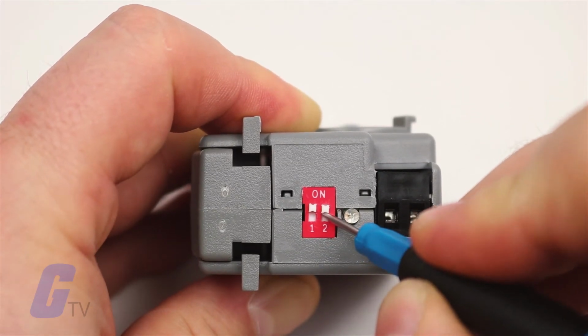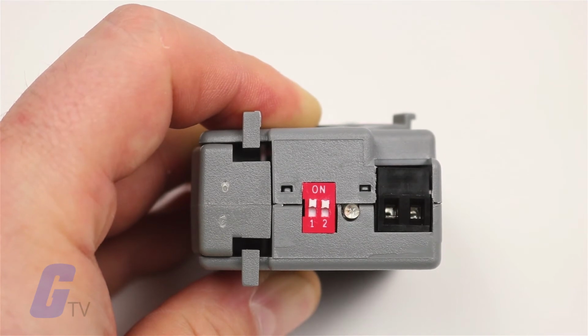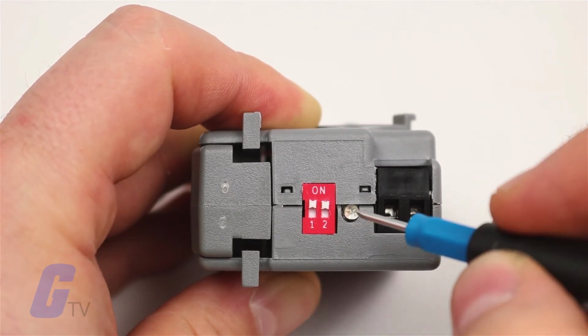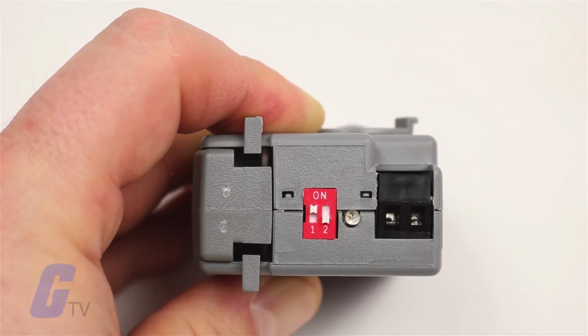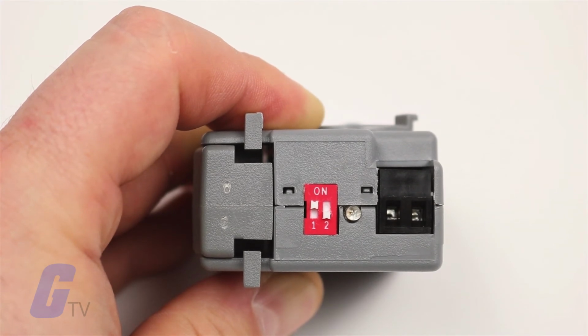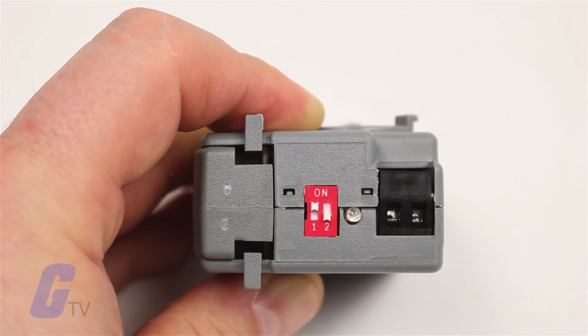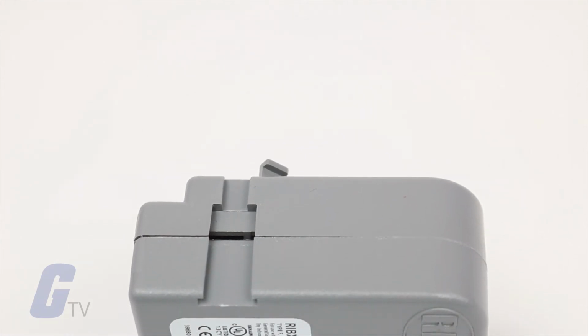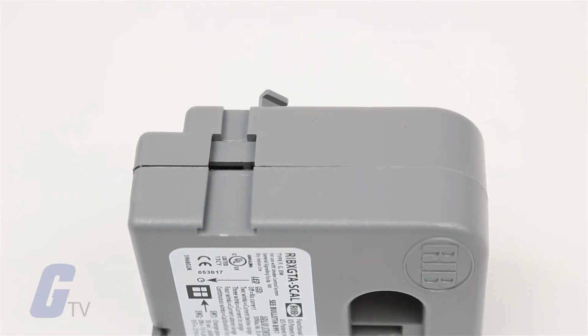SW2, in the on position, provides a 15% plus or minus 3% differential. In the off position, it provides a 25% plus or minus 3% differential. SW2 can be selected at any time and does not affect the threshold setting.